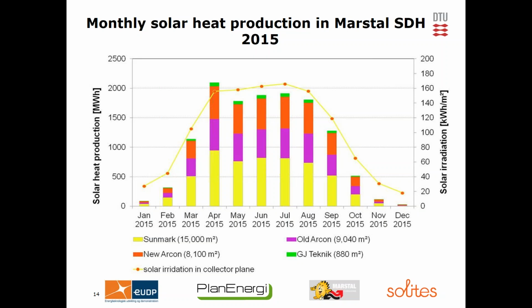But another important reason is that because of the use of the heat pump, the temperature in the pit storage is decreased to quite a low level, like 10, 15, or 20 degrees. Because of this low temperature level, the efficiency of the solar collector could be increased, resulting in higher solar production in April.